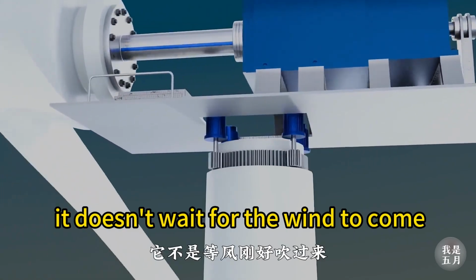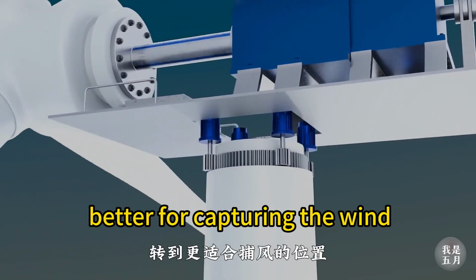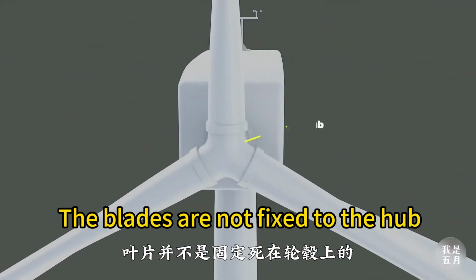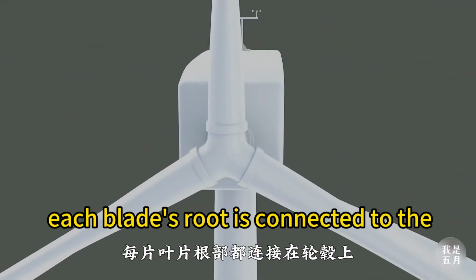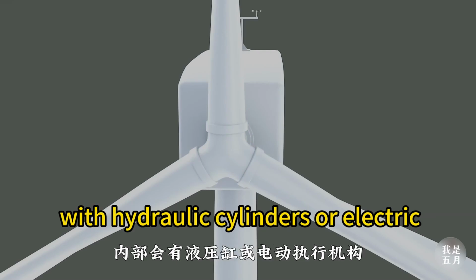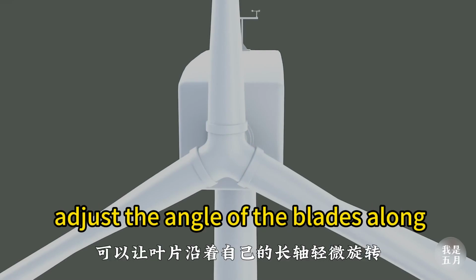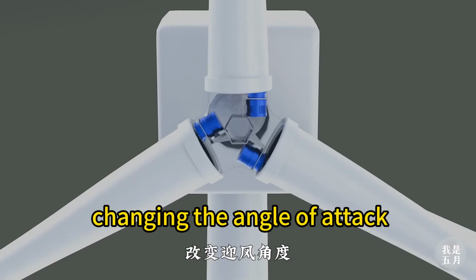It doesn't wait for the wind to come, but actively turns to a position that is better for capturing the wind. Next, let's talk about the pitch system. The blades are not fixed to the hub. Each blade's root is connected to the hub, with hydraulic cylinders or electric actuators inside that can slightly adjust the angle of the blades along their long axis, changing the angle of attack.